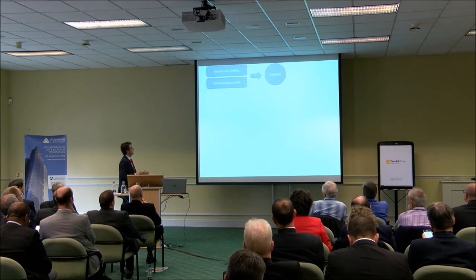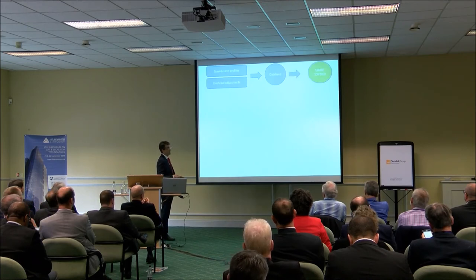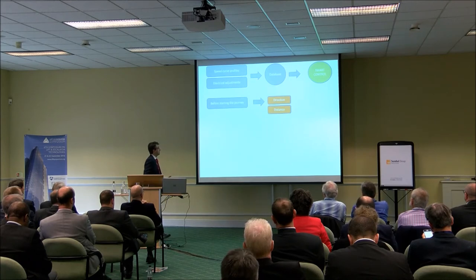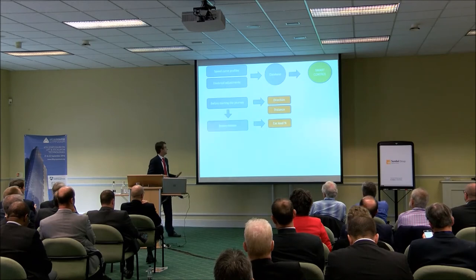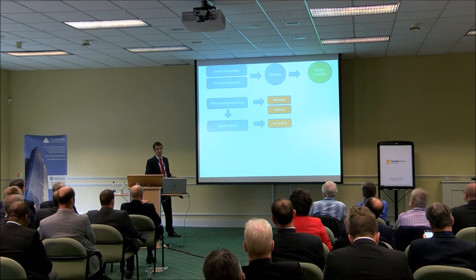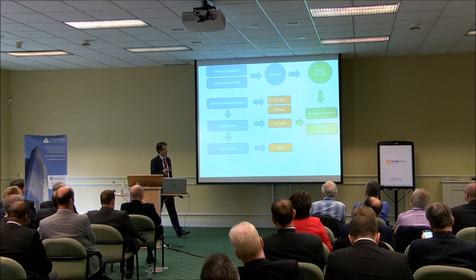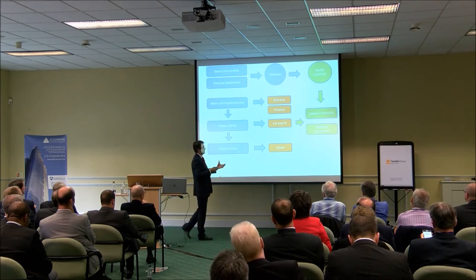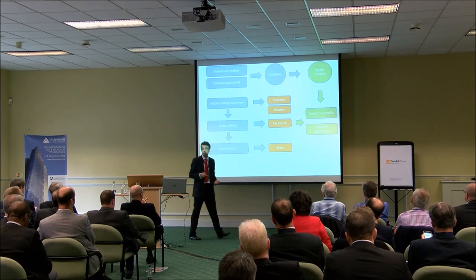We have identified speed profiles and electrical adjustments, and we could generate a database and a smart control. How does it work? The smart control, before starting the journey, already knows the direction and distance. Once the brakes release, we can calculate the car load, choose the speed point for the journey, and then the smart control goes to the database and selects the speed and curve profiles and the electrical adjustments of the variables.